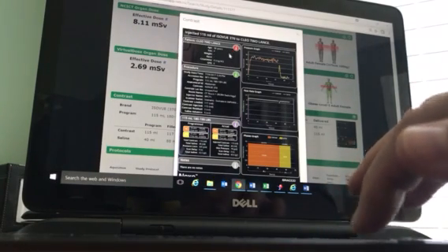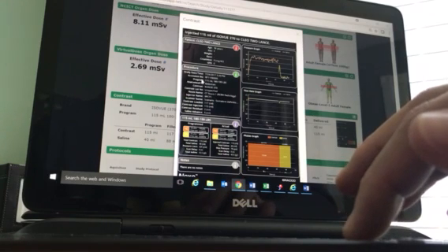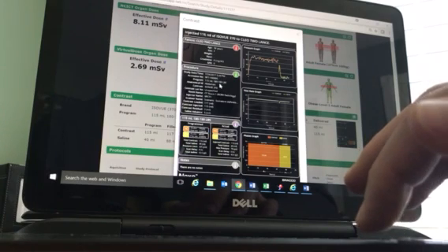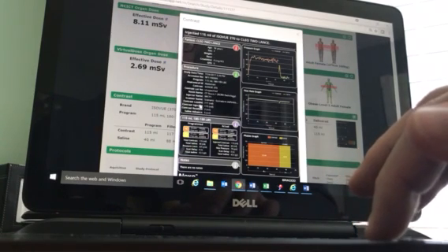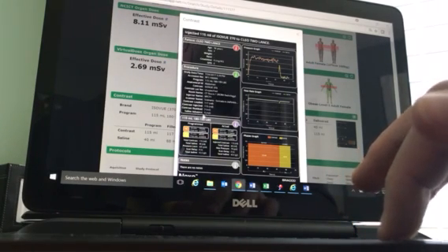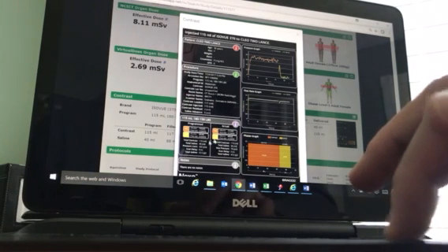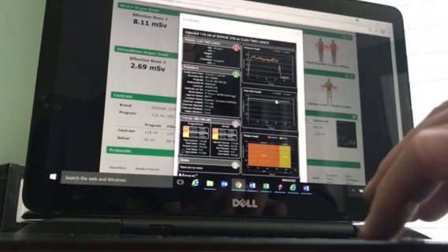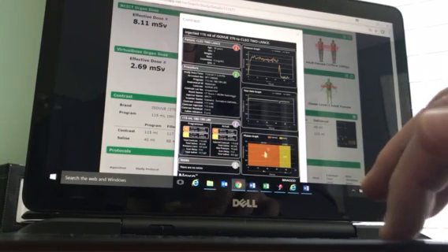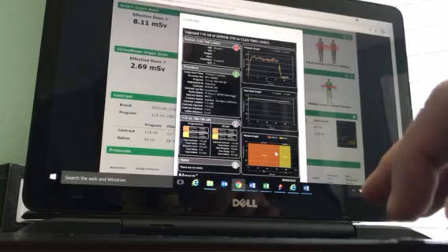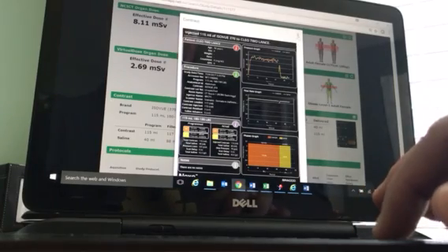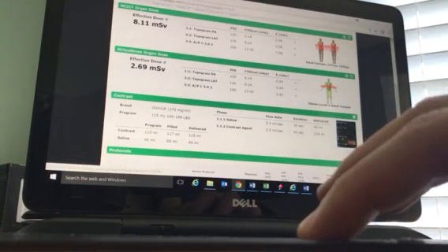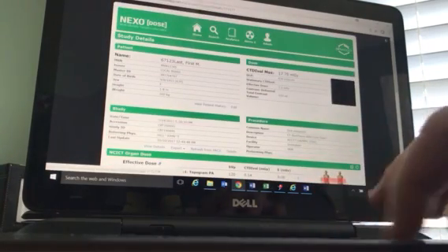Again, you get the patient demographics, you get the procedure that was done, the contrast that was used, the program that was used for those particular patients, contrast loaded, contrast injected, any residuals for contrast and saline. You can see all of that information down here. You get your pressure graph throughout the exam. You get a flow rate throughout the exam and the phase graph throughout the exam. And that gives the doctor an indication of how the injection went as well, so they don't necessarily have to pick up the phone and call the technologist to find out why.